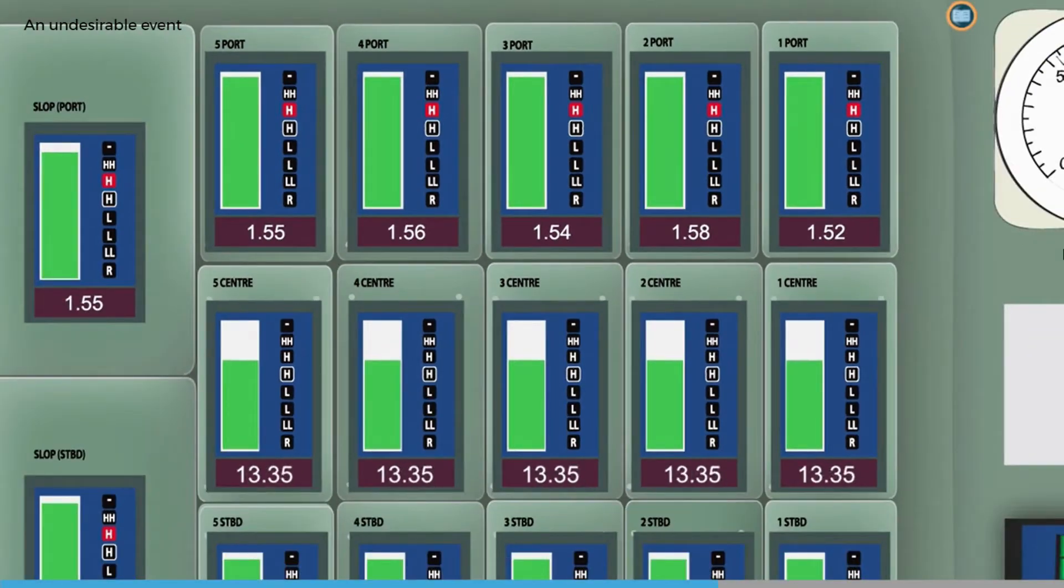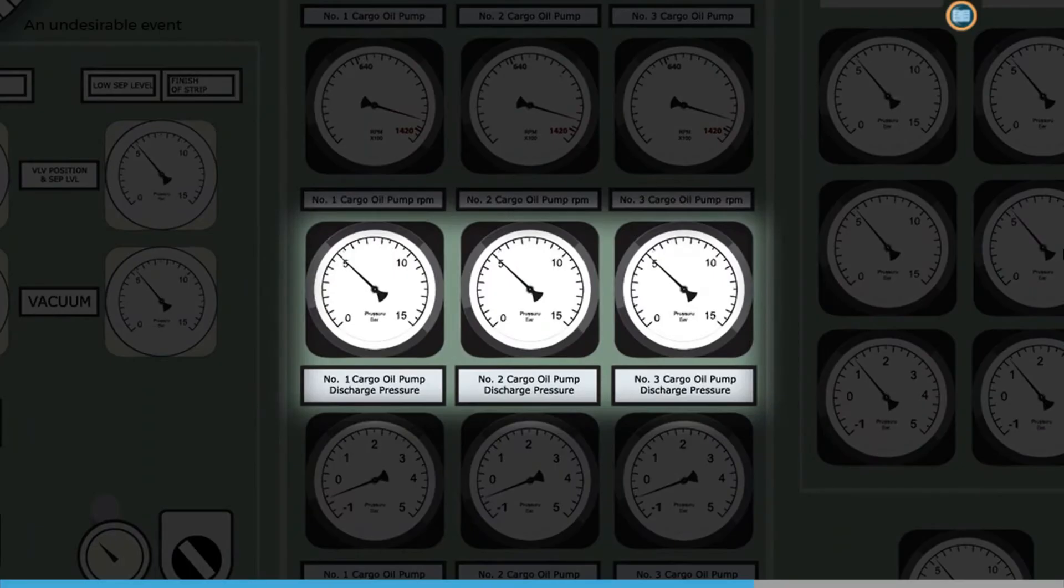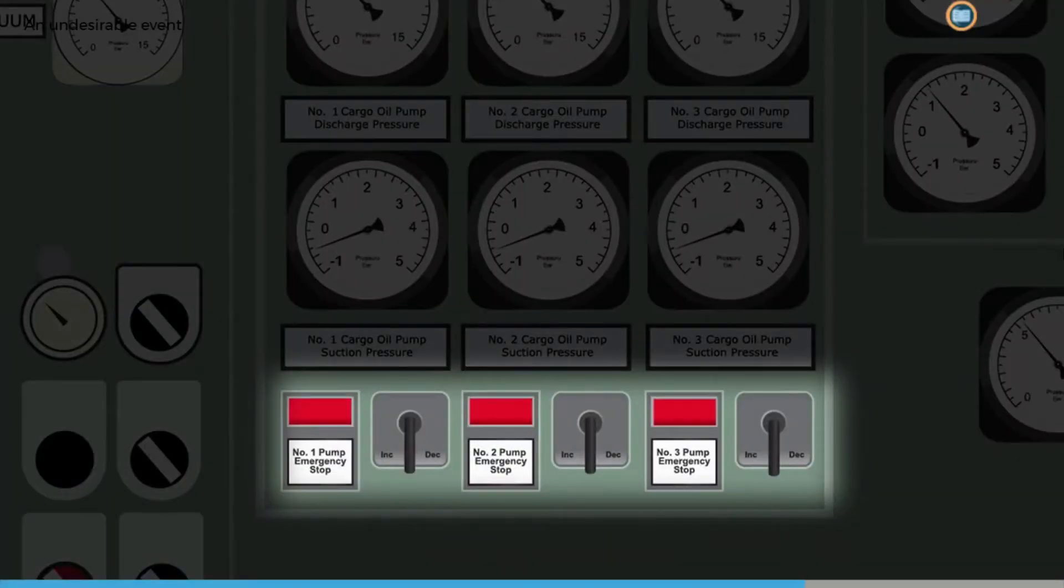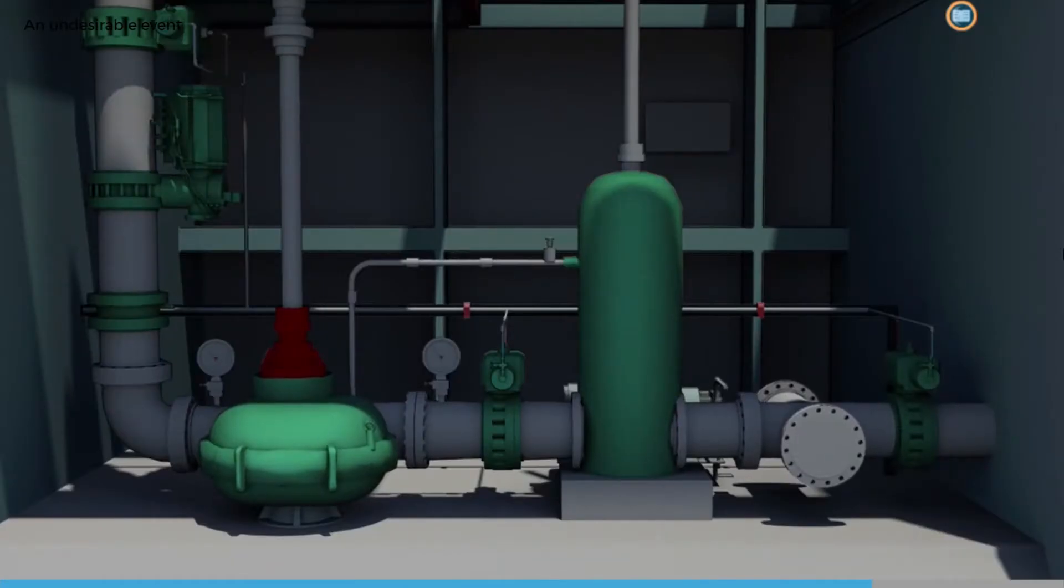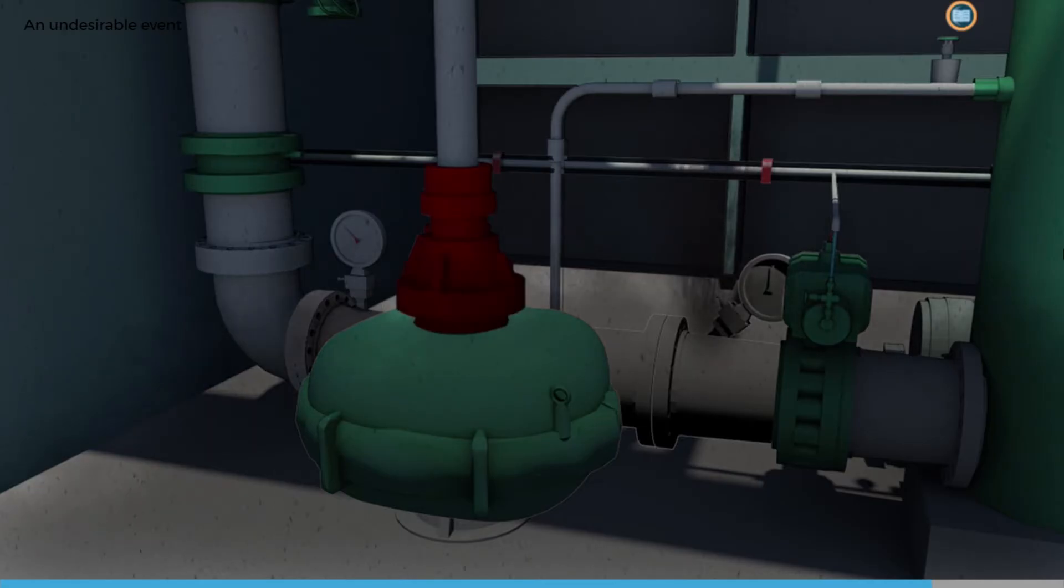When the tanks were close to empty, the pumps suddenly became very noisy and the pump discharge pressure gauge readings fell. This indicated that it was time to stop No. 2 pump as per the plan and slow down the other pumps as the tanks were nearly empty. Unfortunately, cavitation subjected the already weakened pressure gauge pipe to sudden vibration. This was enough to make it shear and spray crude under high pressure all over the port side of the pump room.